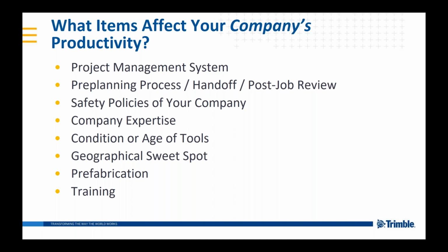I can remember specifically at one time, when we brought a vendor in, and it was Hilti, and they were showing us their new speed hanger, where the side of a clevis hanger opened up like a door, so that you put in all of the hangers and then come back with the doors open or the side open on them, put your pipe in, close the doors on the hanger. So this kept you from having to support the hanger and awkwardly try to get that clevis around it. So that type of training always helped the foremen on new material installations or joining processes.